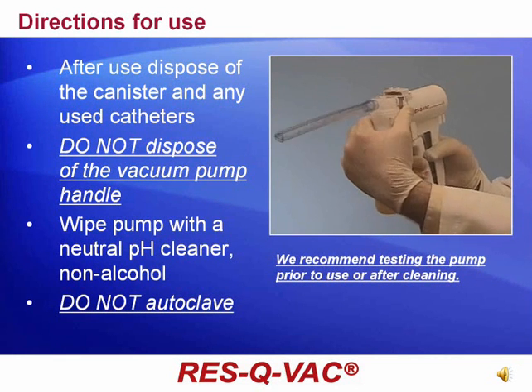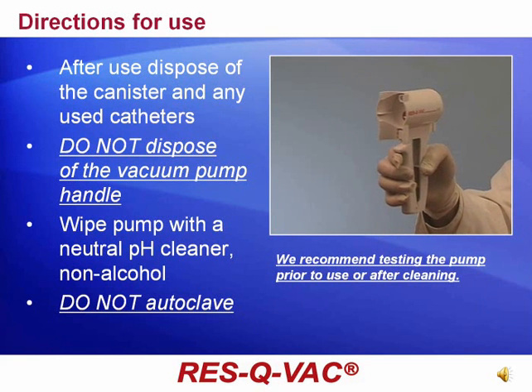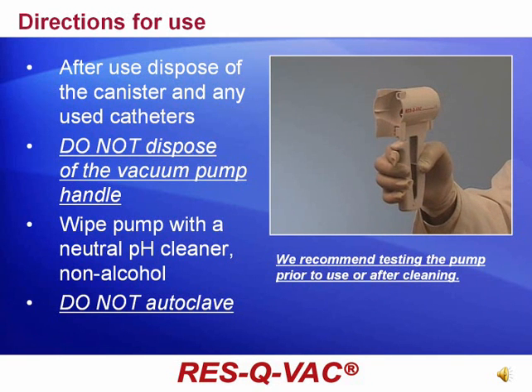After use, dispose of the canister, adapter, and any used catheters. Do not dispose of the vacuum pump handle. The vacuum pump handle is safely reusable and can be wiped down after each use with a neutral pH cleaner, non-alcohol.